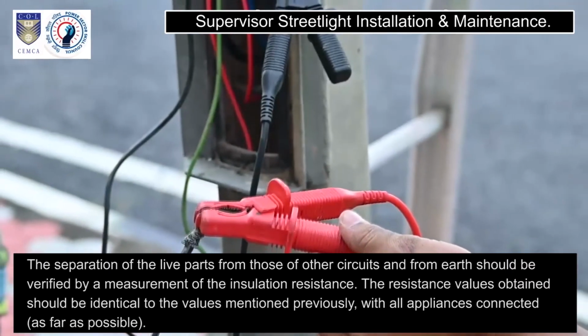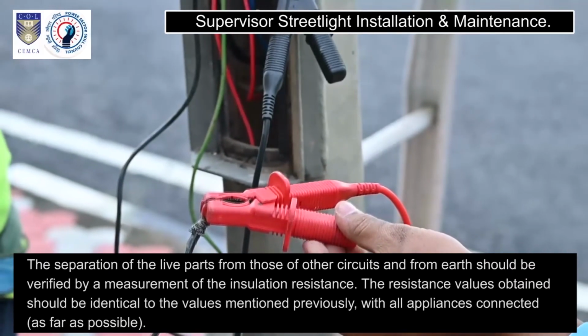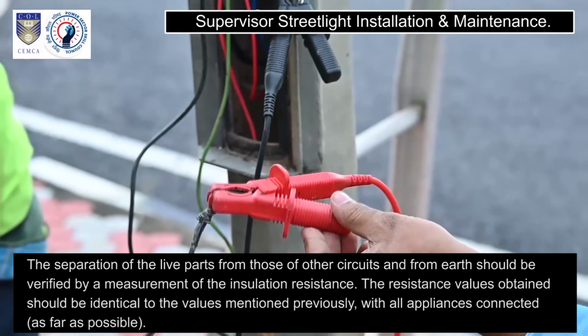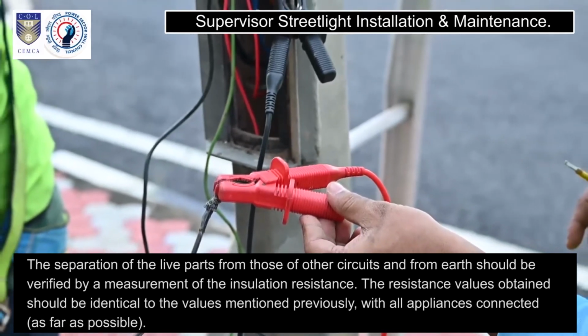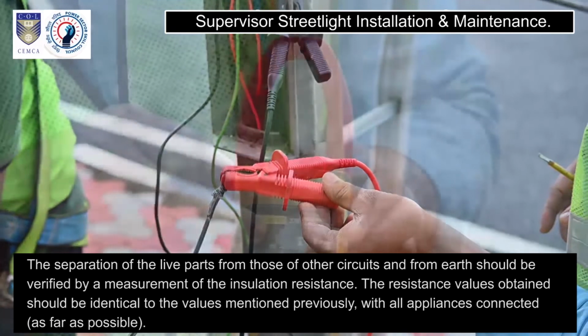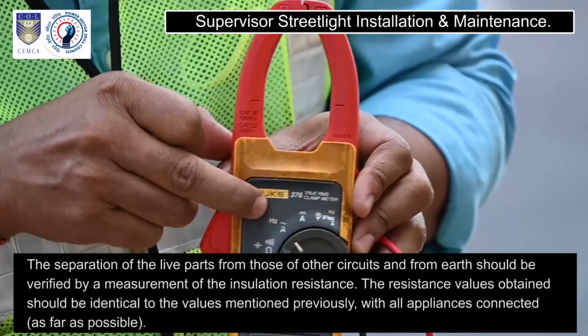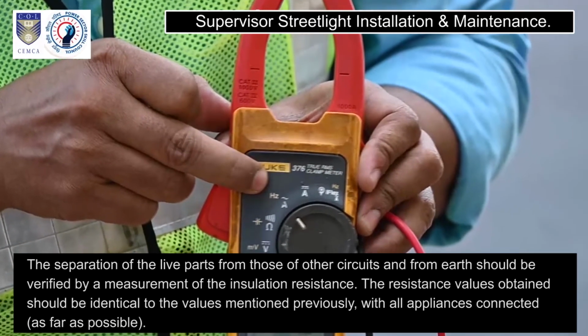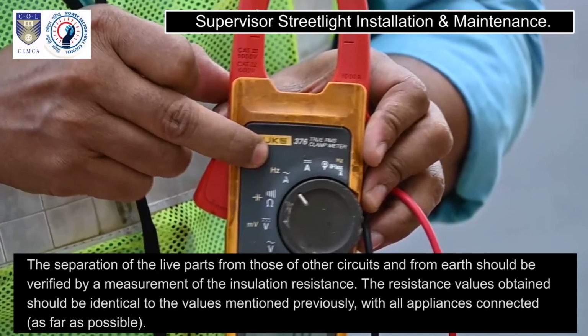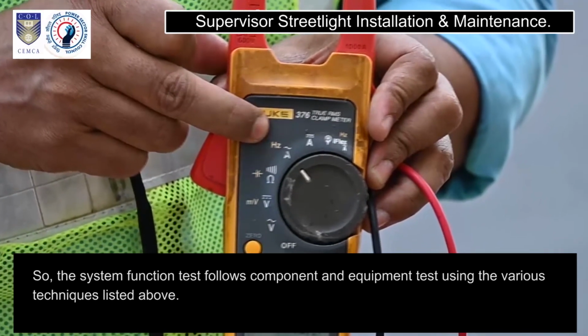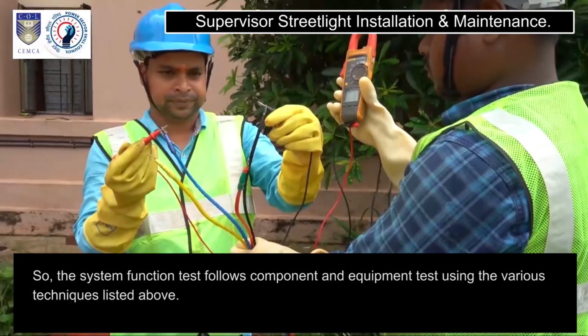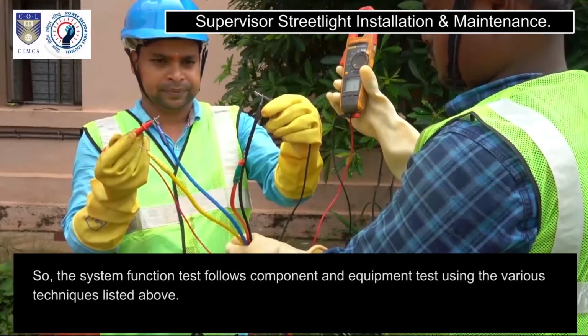Separation of circuits. The separation of the live parts from those of other circuits and from earth should be verified by a measurement of the insulation resistance. The resistance values obtained should be identical to the values mentioned previously, with all appliances connected as far as possible. So the system function test follows component and equipment test using the various techniques listed above.